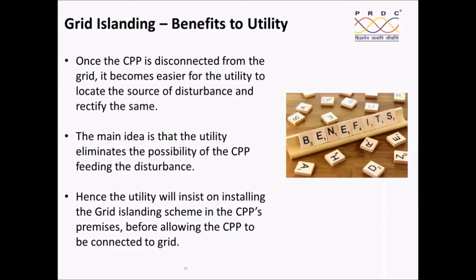Once the CPP is disconnected from the grid, it becomes easier for the utility to locate the end source of the disturbance and rectify the same. Therefore, whenever the captive power plant is there and there is a major disturbance in the grid, if the CPP gets isolated, most of the utilities, whenever they have an industrial system getting connected and there is a captive power plant, ensure that there is a proper islanding scheme.